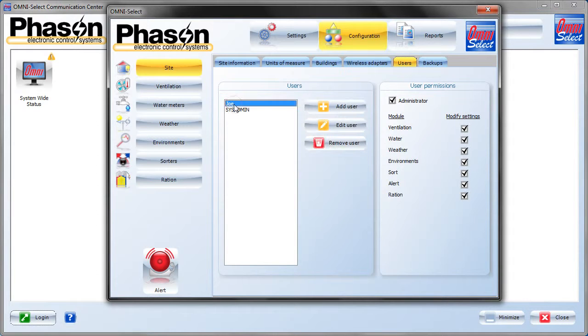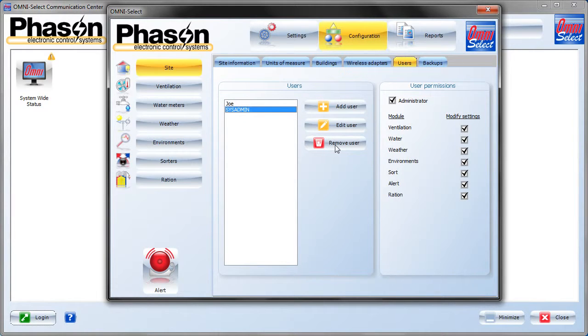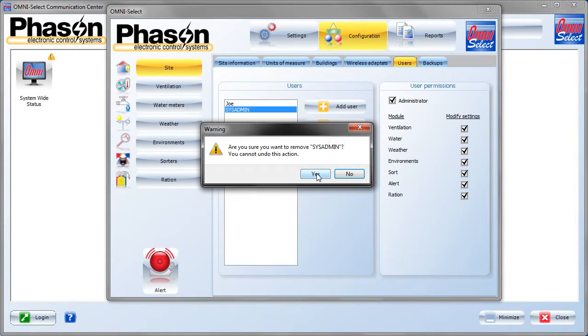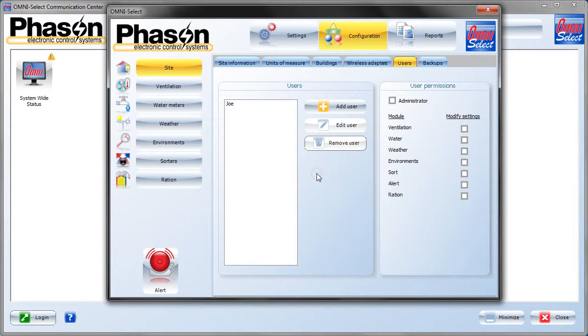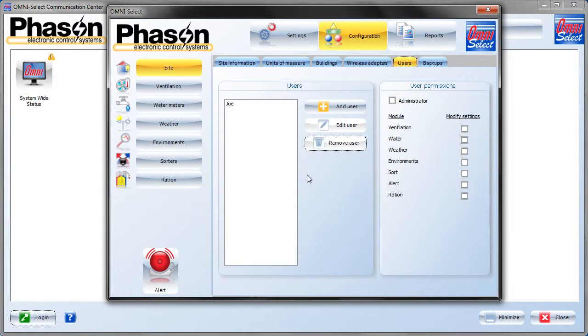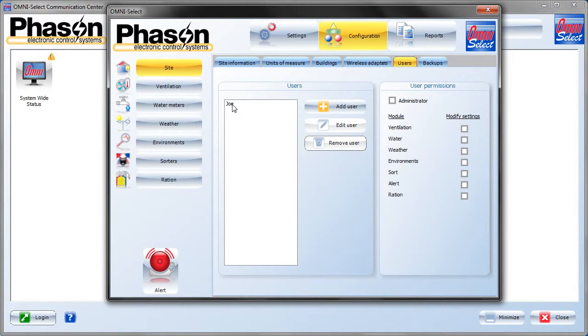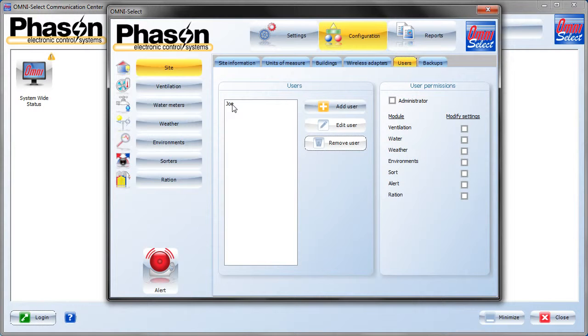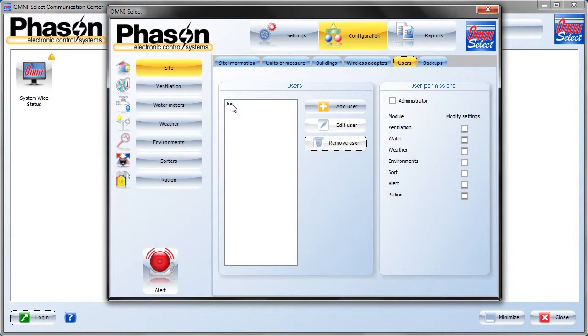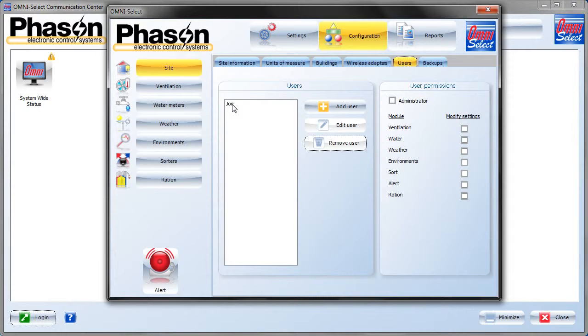Now that we have another administrator user, we can go to the sysadmin and actually just remove that altogether. If you want, you can always put that back in. The system will never let you take out all the administrator users. There will always have to be one in there. The reason we want to change the user from sysadmin to an actual person is it will protect against unauthorized access. It also provides an audit log for each user with changes that they made while they logged in. It's better to have all the users that will access this system to have their own name in there instead of everybody using the sysadmin, and that way you can track who did what and when.